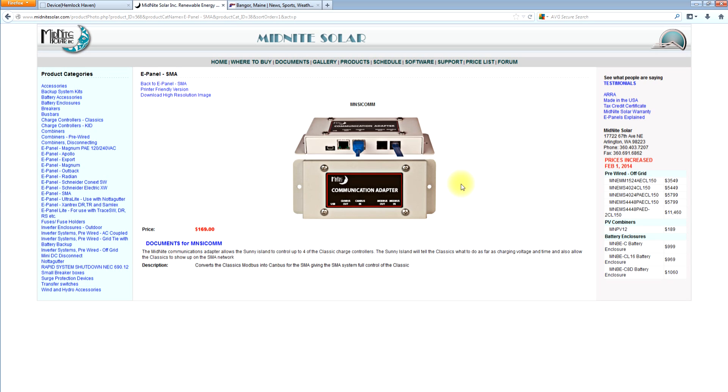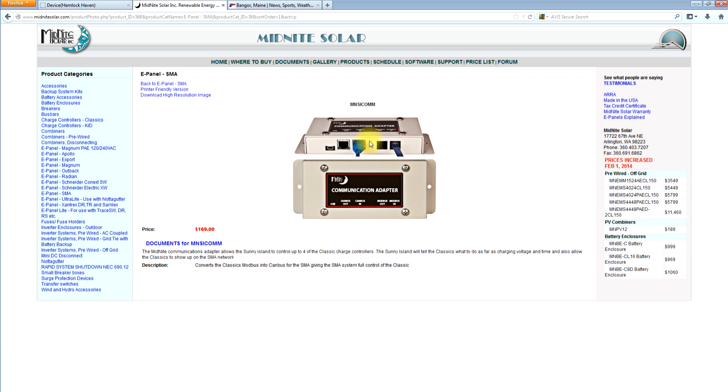And the Sunny Island tells the classics what to do. Sets their charging voltages. Gives them their battery temperature. Everything. So basically all you have to do is initially set the classic for 48 volts, set it for SMA mode, plug the cables in, and the Sunny Island takes control and does everything that it needs to do and treats it as if it was its own charge controller. So that's a real elegant solution if you're doing a grid tie with battery backup or you're doing a mixed hybrid system with some AC coupled and some DC coupled. This is a really nice solution because it then puts the Sunny Island in control of all battery charging. So the Sunny Island is telling the Sunny boys what to do and the classics what to do. And the two just work together in perfect harmony.